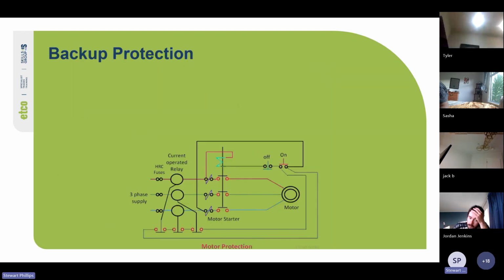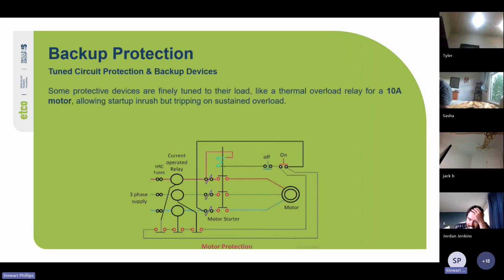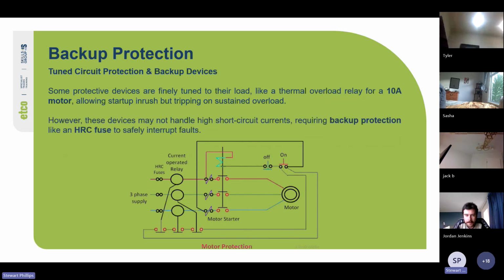Cool. So you've got backup protection. So, tuned circuit protection and backup devices. Some protective devices are finely tuned to their load, like a thermal overload relay for a 10 amp motor, allowing startup inrush but tripping on a sustained overload. However, these devices may not handle high short circuit currents, requiring backup protection like an HRC fuse to safely interrupt faults. So that's what we were talking about before with the thermal overload.